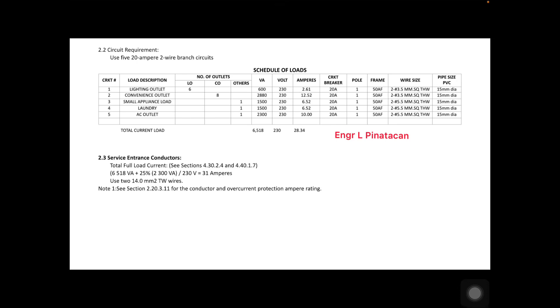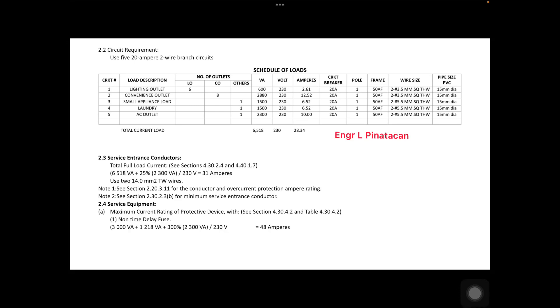We verify the conductor and overcurrent protection per section 2.20.3.11, and the minimum service entrance conductor per section 2.30.2.3.B of PEC 2017. Next, we check the service equipment and determine the maximum current rating of the protective device, referencing section 4.30.4.2 and table 4.30.4.2.